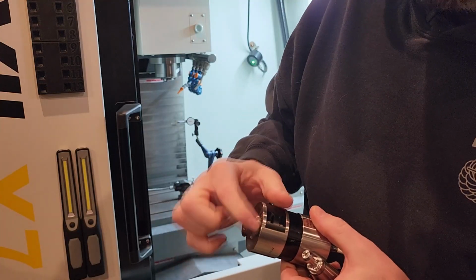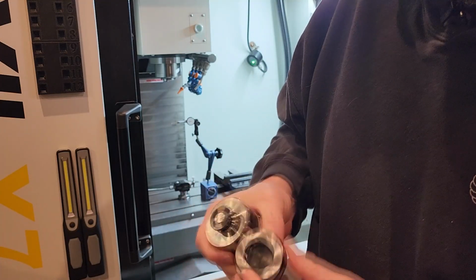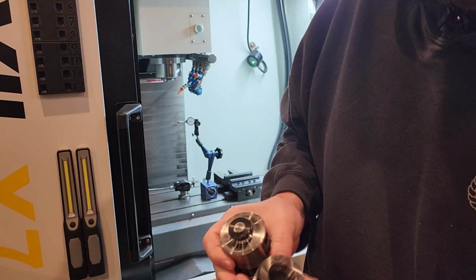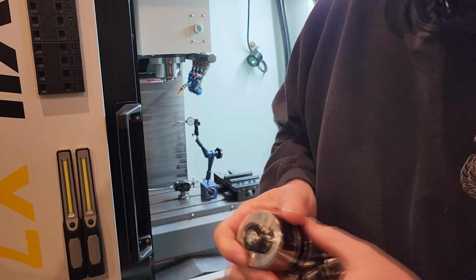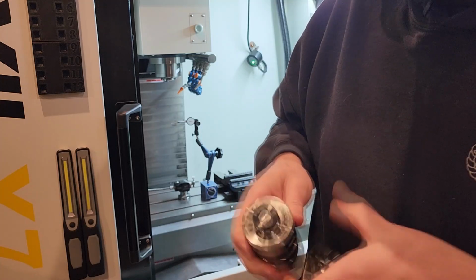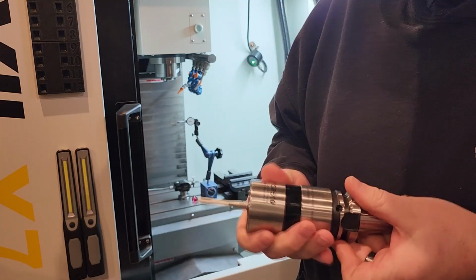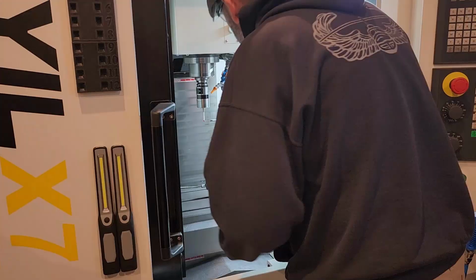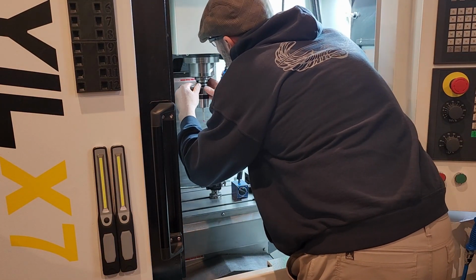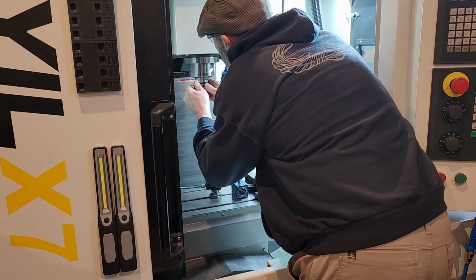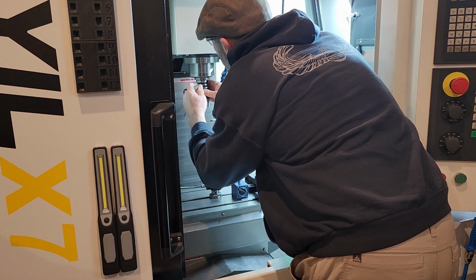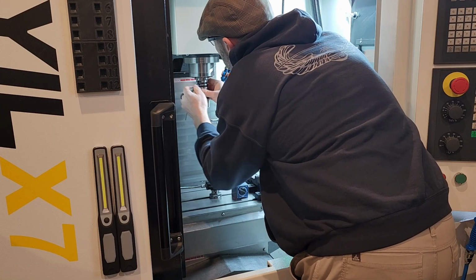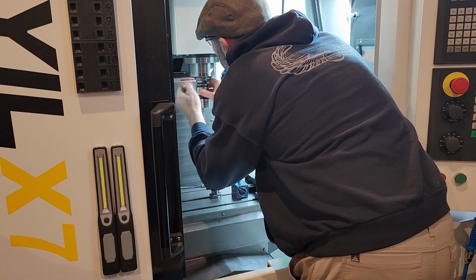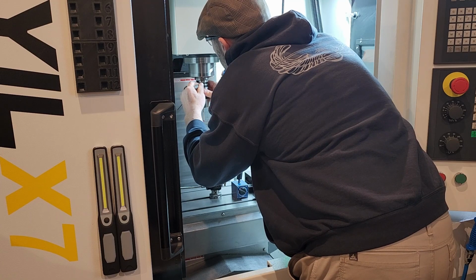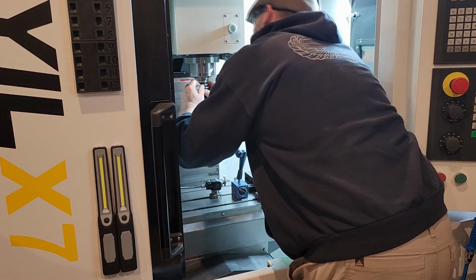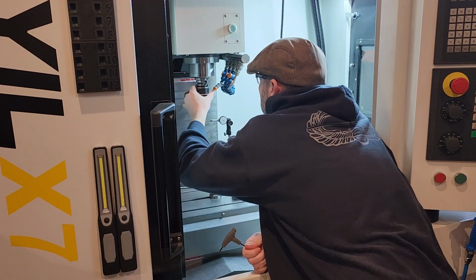This is what we're working with. As you can see here, there's a circular dovetail that captures the screws. As the screws are tightened, the run out of the probe is adjusted, and simultaneously the probe's body is drawn towards the shank. This is a delicate and most times time-consuming process. With 3 screws, you only have 120 degrees of adjustment per screw point. It's best not to overly loosen the screws as the weight of the probe will fight against you. With a bit of practice, I suppose it can be done, but it takes expertise and patience.